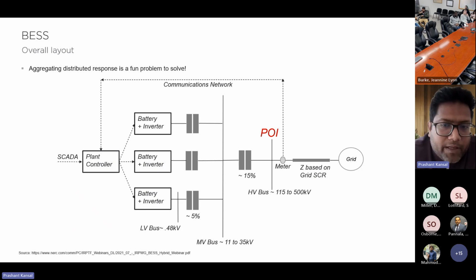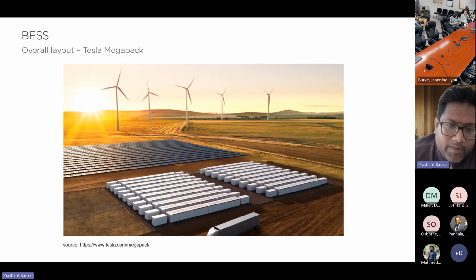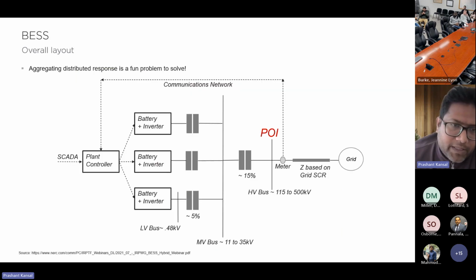Here's a typical structure of a battery storage plant: you have a plant controller on the left side, which gets a SCADA command from the grid operator. Then there are multiple inverters, as you see in the photo, multiple Megapacks, each with inverters and batteries inside those white boxes. And even within those boxes, we modularize it even further.